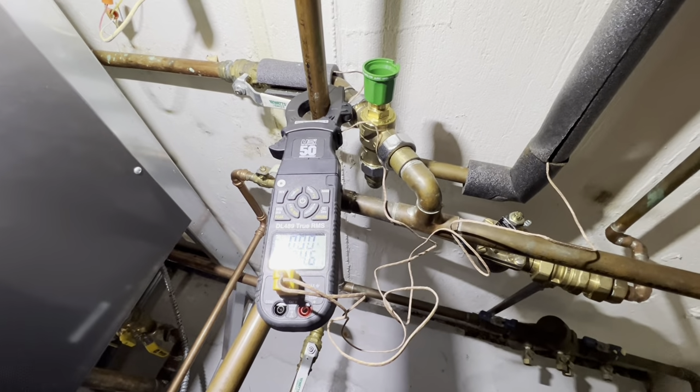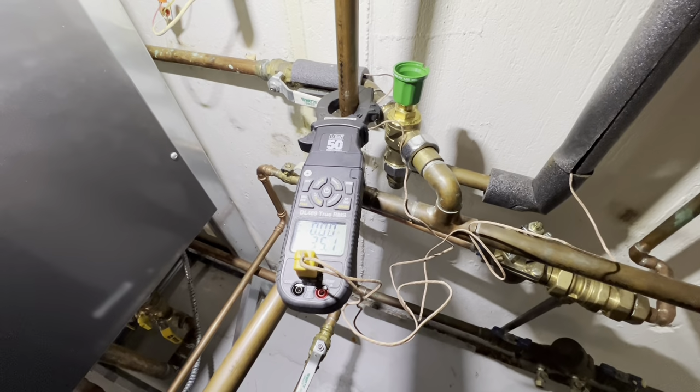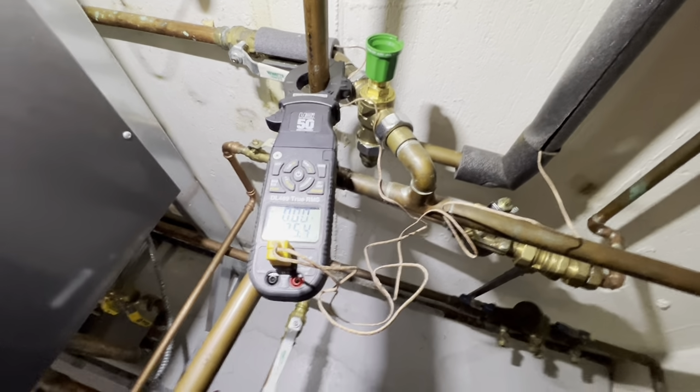So I'm going to see. I don't think I have this. I wonder if a Caleffi will fit right in its place, but I don't think so. And just like that, I thought I was going to need NTI tech support for this one, but nope. It was a simple mixing valve swap, so I'll show you the valve. We're going to do a combustion test to make sure it's burning safely and test our heating.